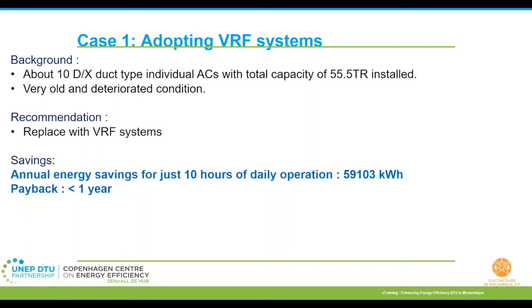So case one is about adopting VRF systems, or variable refrigerant flow systems. A VRF system typically consists of an outdoor unit with multiple compressors and different types of indoor units for different zones. It also comes with a highly sophisticated electronic controls center, which can enable zone-wise climate controls.